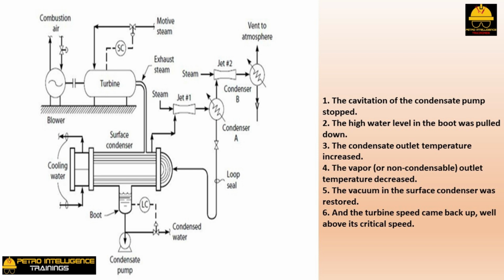The turbine and blower began to vibrate. The bearings were damaged. The turbine's rotor became unbalanced. A rotating element on the air blower touched a stationary component in the blower's case. The stationary component broke off and wrecked the blower. That was the end of K805. By what law of nature was the turbine forced to slow exactly to its critical speed? You see, dear gentlemen, life is perverse. And if anything bad can happen, it is going to happen to anyone.